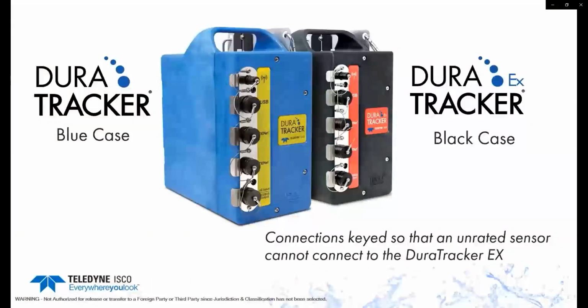Let's go ahead now and take a look at the two different styles of DuraTrackers that we have. The DuraTracker in the blue case is the non-IS version, so that's the standard one. The one in the black case is the DuraTracker EX. One thing you'll note on this is the connections on the black unit, or the EX unit, are keyed so that you cannot connect an unrated sensor to the DuraTracker EX. Only the EX sensors will connect to the DuraTracker EX.